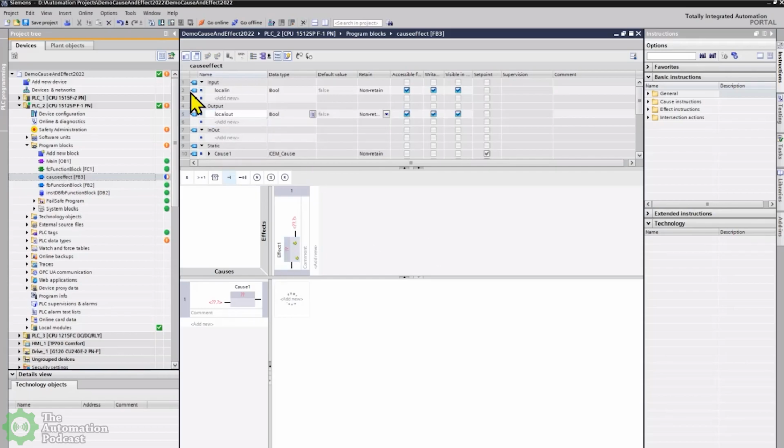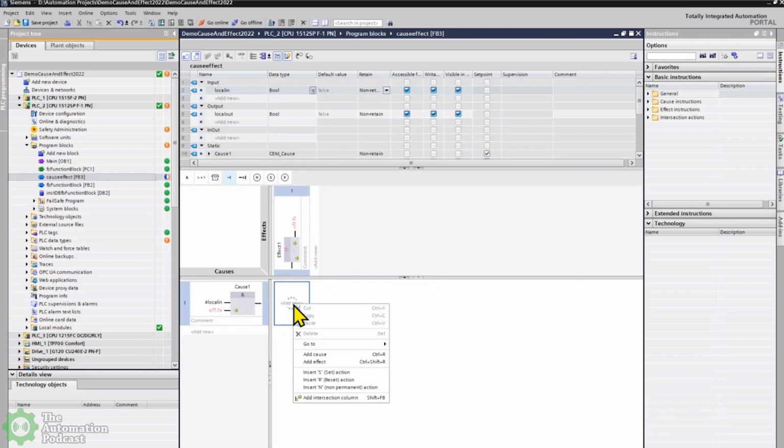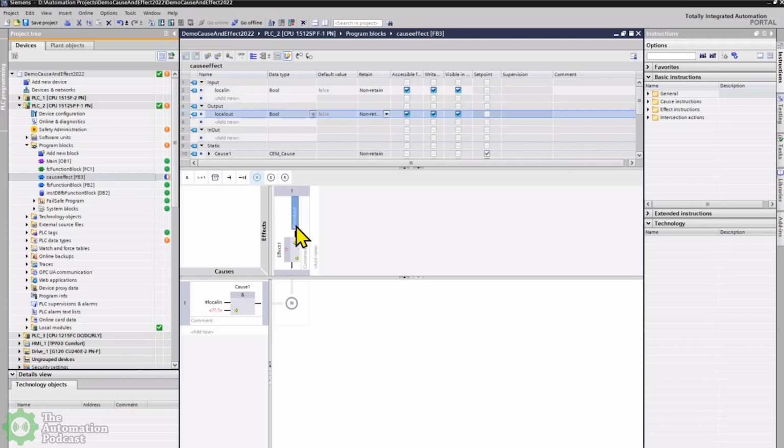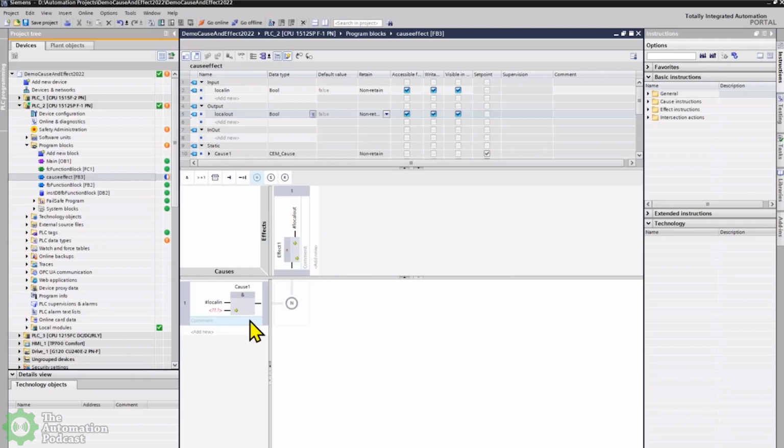And basically, just like ladder logic, I can parameterize the cause, give it an instruction, and then define a set or matrix function, and then do the same across the top. Define the output, connect the output, give it an instruction like equal, which is the easiest one to do for that one. And then basically I've got that these conditions drive to that output.